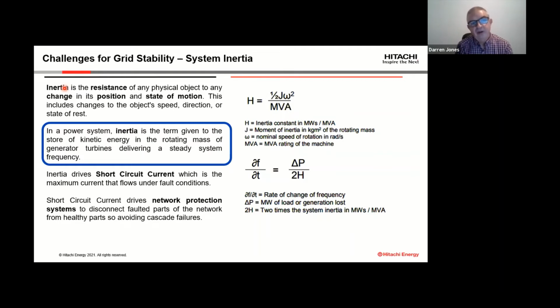The inertia is just the term given to the store of kinetic energy in the rotating mass of those thermally driven generators. It's an absolutely fundamental feature of the way those large power producers operate, the way they've always operated on the system. It's just absolutely key part. The inertia that's been provided essentially for free, just by virtue of the fact of the design of these large power stations. The system has taken the benefit of having free inertia just by virtue of the way it's designed. And this is what we're now losing with this move away from fossil fuel generation over to renewable energy generation. And it's the inertia where the store, as the slide says, the store of kinetic energy in the rotating mass of that generator turbine.